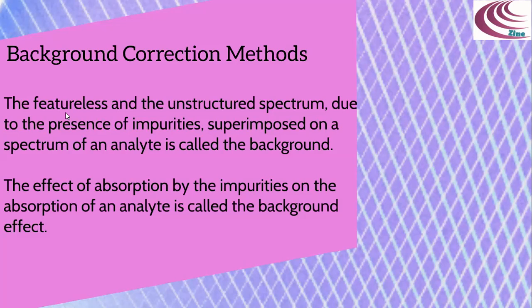The interference due to the background absorption can be eliminated by advanced techniques like derivative spectrometry and difference spectrometry. In addition, there are also simpler techniques available which have the common feature that measurements are performed at other wavelengths as well as at the absorption maximum for an analyte, and the background corrections are done mathematically.